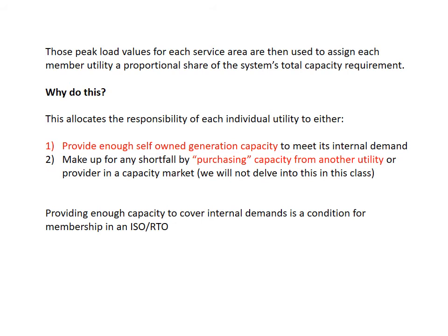It's the marker that PJM uses to tell individual utilities, like, look, you need to build more capacity or pay somebody else to build capacity because your reserve margin has gone down, right? Your demand has increased, your capacity has stayed the same, and your reserve margin is less than 15%, so you need to build some more. And it's also a big part of how a lot of other transmission planning requirements get done as well.